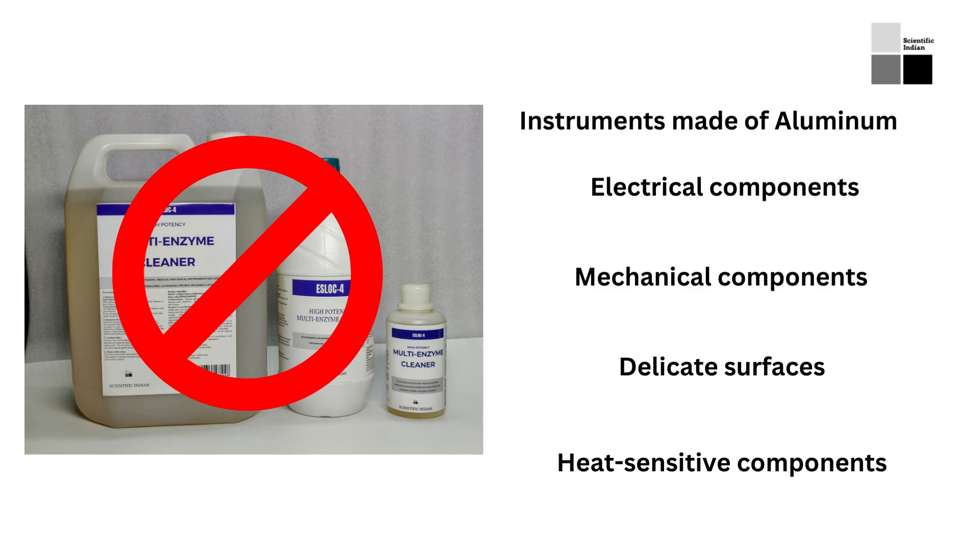Pre-cleaning surgical instruments refers to the initial step of cleaning where the instruments are rinsed under running water to remove any visible debris or blood. This step is done before the instruments are soaked in the ESLOC-4 multi-enzyme cleaner. The purpose of pre-cleaning is to remove any large particles or chunks of debris that may be present on the instrument so that the enzyme cleaner can more effectively remove the remaining debris. A brush may also be used to scrub away any stubborn debris.